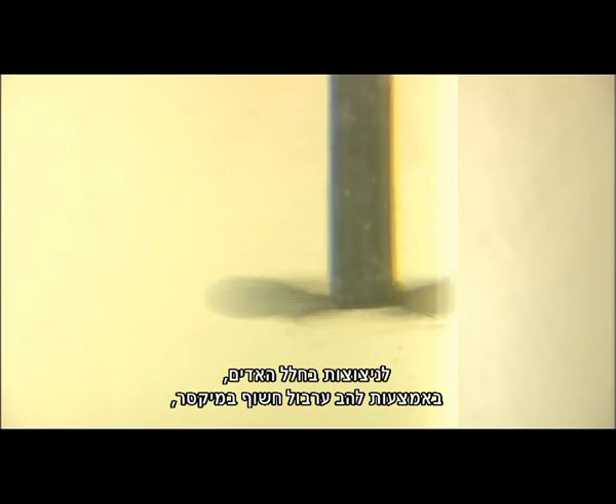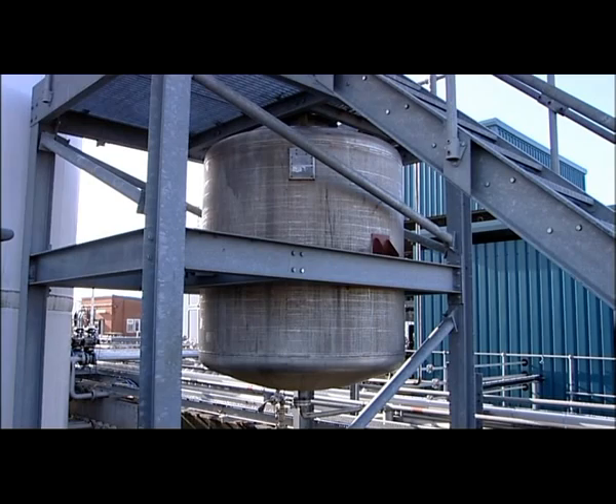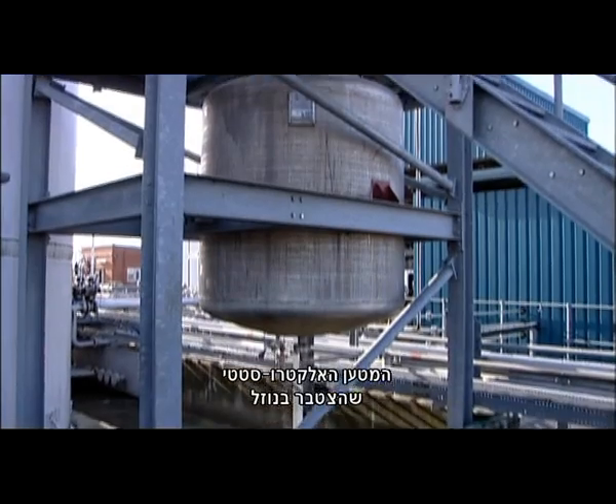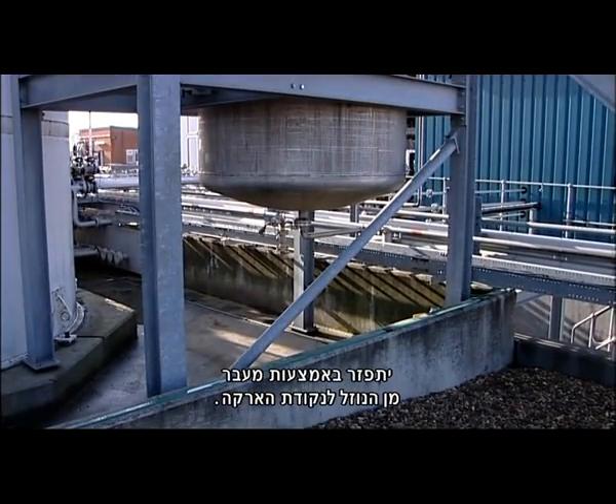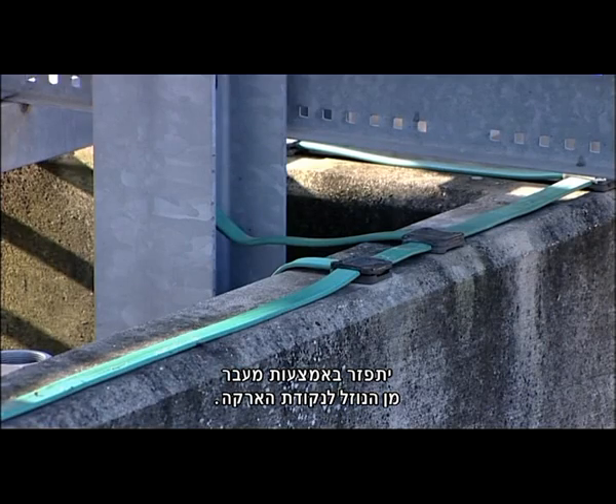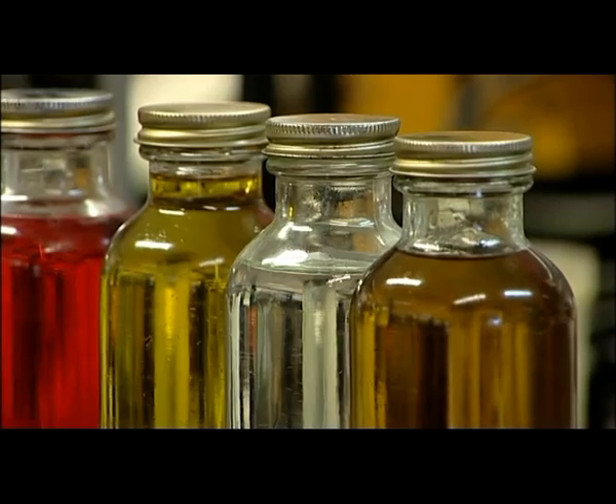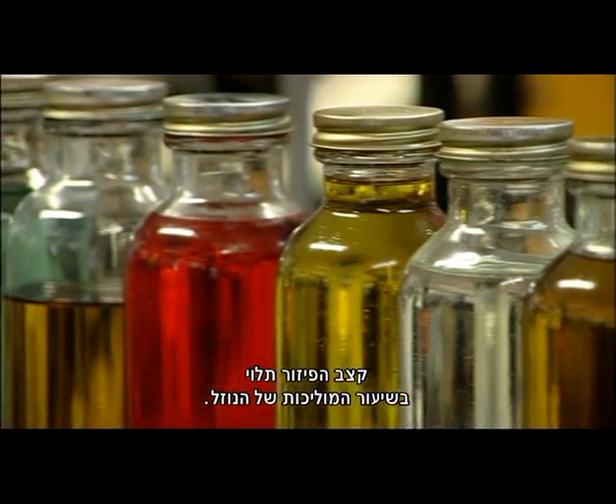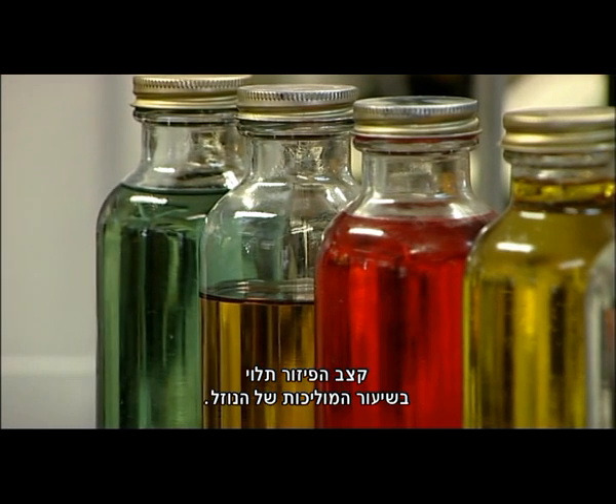With poor conductive liquids, the charge accumulation can cause sparking in the vapor space to an exposed agitator blade in a mixer or to a filling pipe. The electrostatic charge built up in the liquid will dissipate by migrating from the liquid to an earthing point. The rate of dissipation depends on how readily the liquid will conduct electricity.